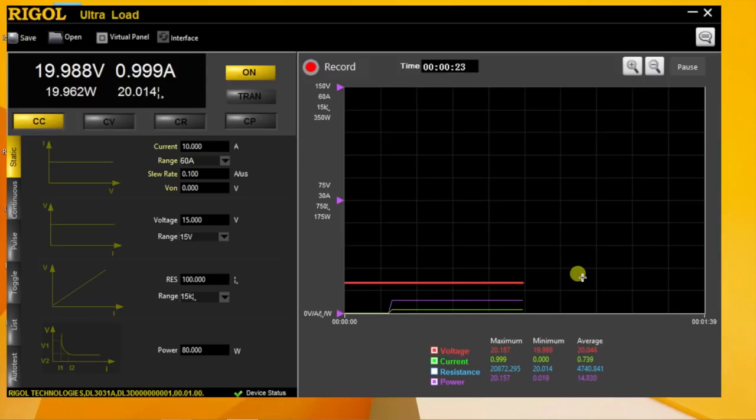This is a great way to record your data for later analysis in addition to anything you might do visually on the front screen. Remember, you also have different ways to stop that test. We can stop it here remotely. In this case, we've programmed it automatically to stop at a certain voltage level, but it can also be programmed for capacity or time.